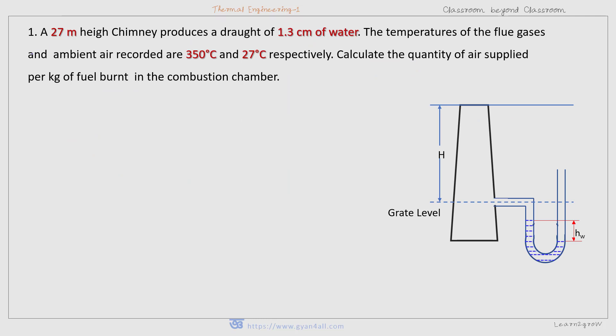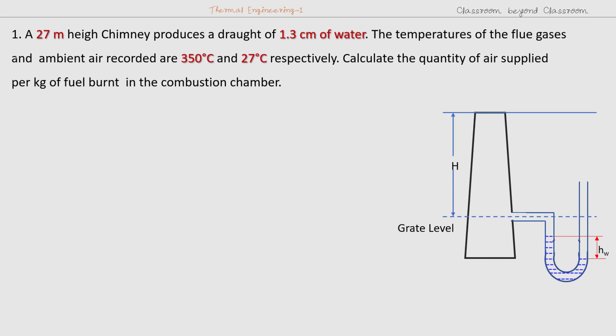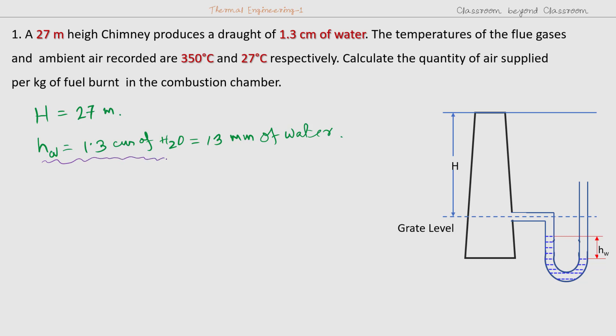The first problem: a 27-meter high chimney produces a draught of 1.3 centimeter of water. The temperature of the flue gases and the ambient air are 350 degrees centigrade and 27 degrees centigrade respectively. We have to calculate the quantity of air supplied per kg of fuel burned in the combustion chamber. From the problem, the height of the chimney H is equal to 27 meters. The drought produced is measured by manometer and is equal to 1.3 centimeter of water, that is 13 millimeter of water, also equal to 13 kg per meter square.